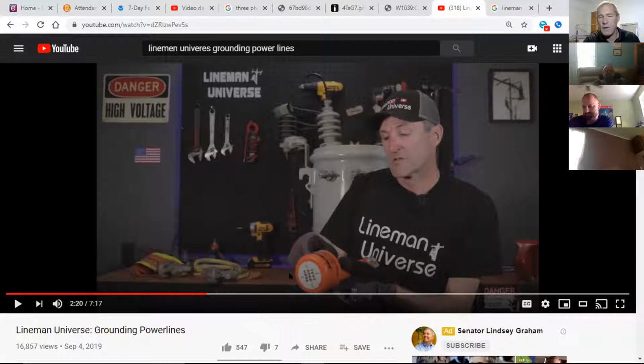I did not like those. The guys working did not like those. You had a solid tone when you turned it on, and whenever you got close to an energized conductor, it stopped. I really don't like that. I like the indication of something making a noise when I get close to it. So test it before you ground it.